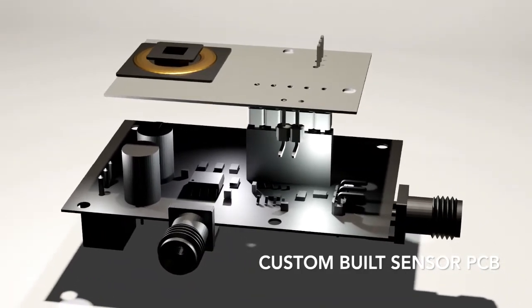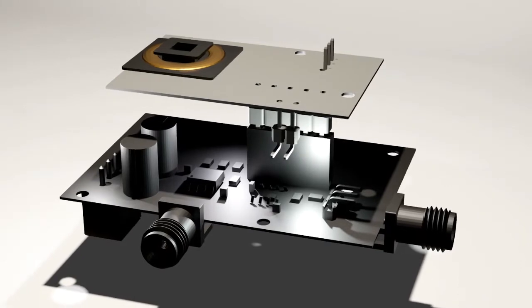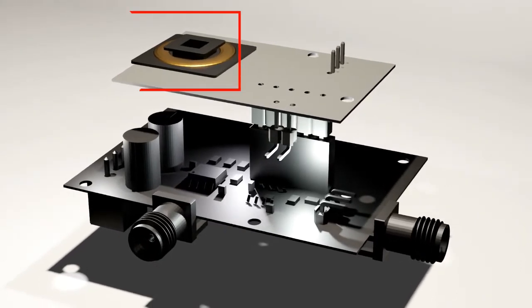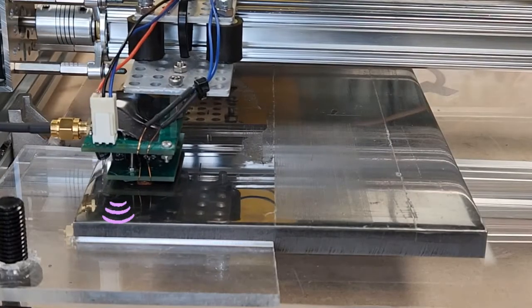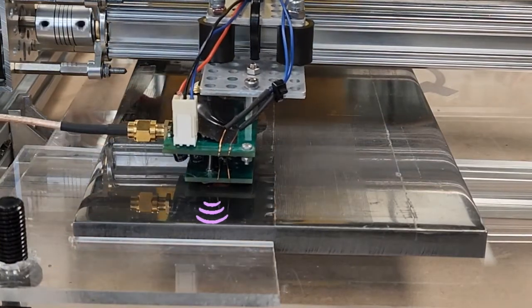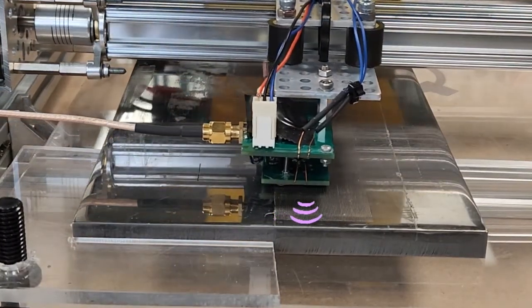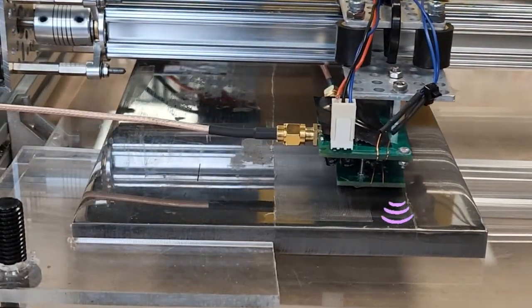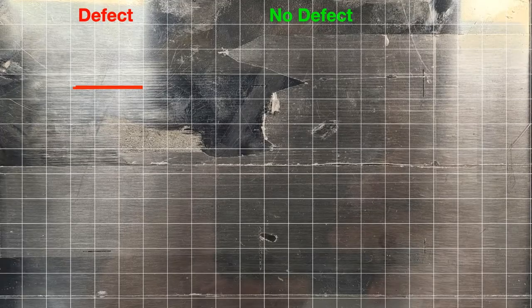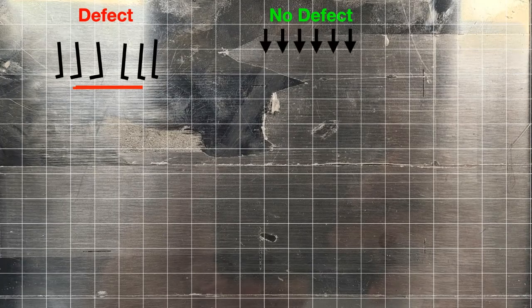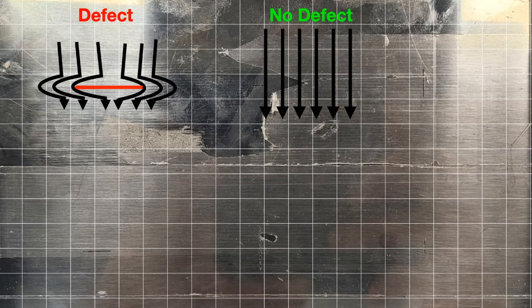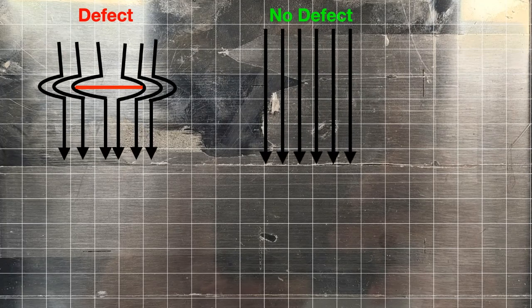The other critical component mounted on the sensor PCB is the Illuminating Electromagnetic Coil. As the probe head moves across the material, the Illuminating Electromagnetic Coil induces a secondary magnetic field in the material. It is this field that the QWHE sensor is measuring, and these values of secondary magnetic field are dependent on any defects present in the material, as the defects interrupt the flow of the eddy currents that create the magnetic field.